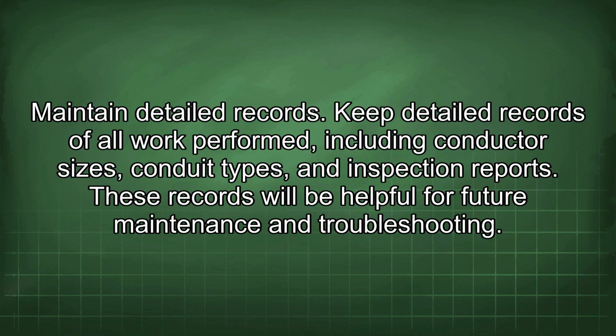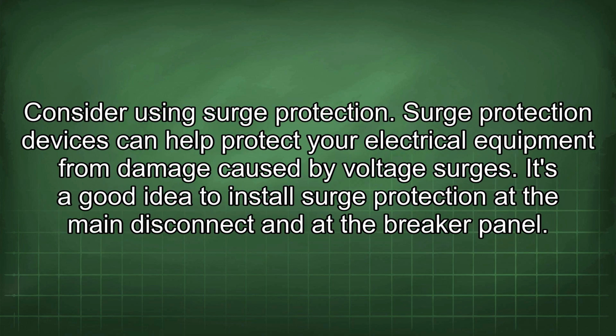Maintain detailed records. Keep detailed records of all work performed, including conductor sizes, conduit types, and inspection reports. These records will be helpful for future maintenance and troubleshooting. Consider using surge protection. Surge protection devices can help protect your electrical equipment from damage caused by voltage surges. It's a good idea to install surge protection at the main disconnect and at the breaker panel.